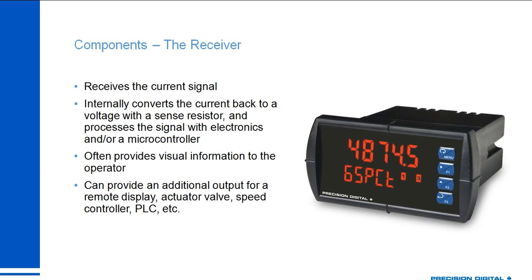Oftentimes either the transmitter or the receiver will have a power supply built into them — that's why sometimes you don't need a separate one. The panel meter shown here, a Precision Digital ProView, if powered from a separate DC or AC voltage, includes an isolated 24-volt power supply for powering your loop. Similarly, there are transmitters powered by an external supply that then provide power to run your loop.